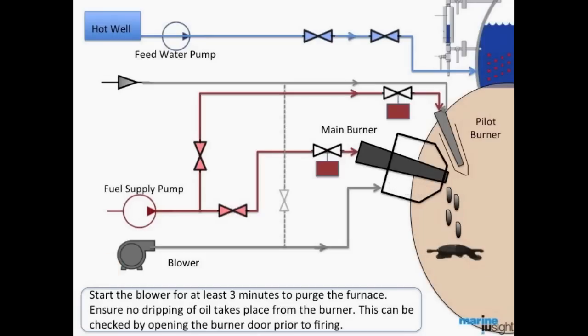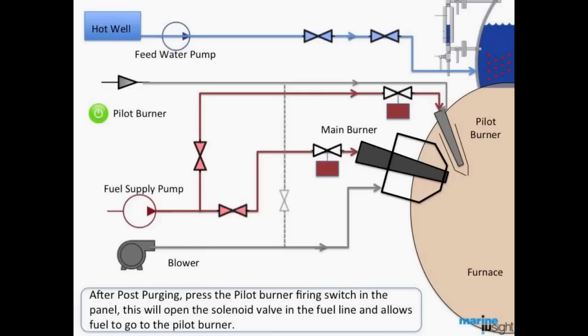Ensure no dripping of oil takes place from the burner. This can be checked by opening the burner door prior to firing. After purging, press the pilot burner firing switch in the panel. This will open the solenoid valve in the fuel line allowing fuel to go to the pilot burner.